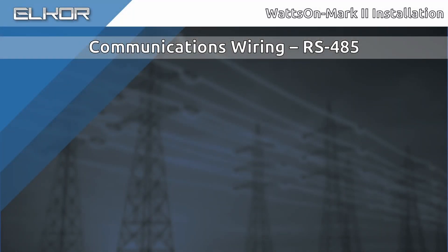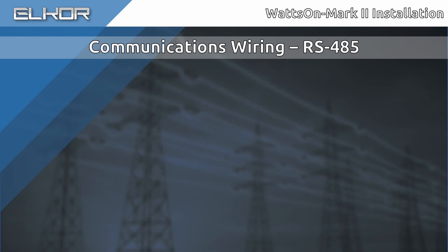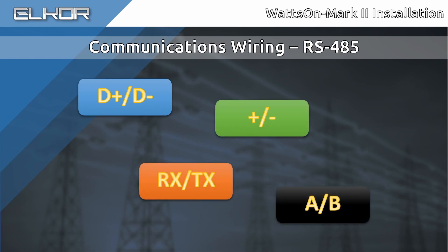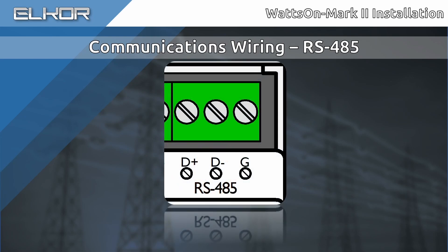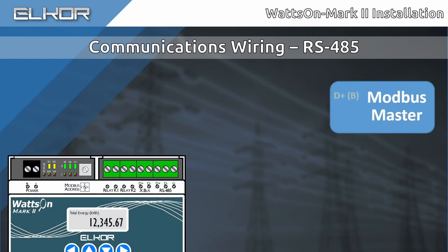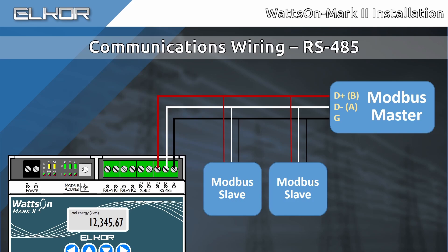When connecting RS-485 equipment, a quality twisted-pair cable should be used. Consider a shielded cable, especially for longer runs. It is important to note that there are a number of different nomenclatures used by manufacturers to label the RS-485 terminals. Refer to each device's manual to understand the suggested connections. The WattsOn Mark II uses D-plus and D-minus designations for the RS-485 port. Generally, D-plus connects to B and D-minus connects to A on other devices. While a ground connection is not strictly necessary, it is recommended in most applications. Observe the same wiring methodology for any other RS-485 equipment on the bus. Ensure to set the Modbus address, sometimes known as the Unit ID, on the meter using the DIP switch or the display to the desired address. Each device on the RS-485 Modbus chain must have a unique Modbus address.